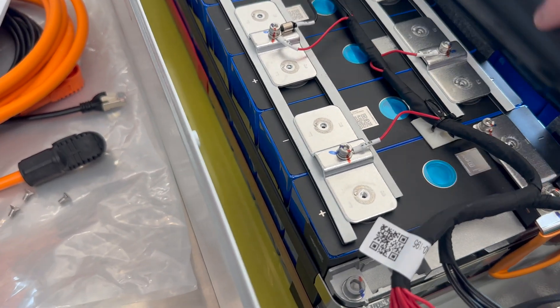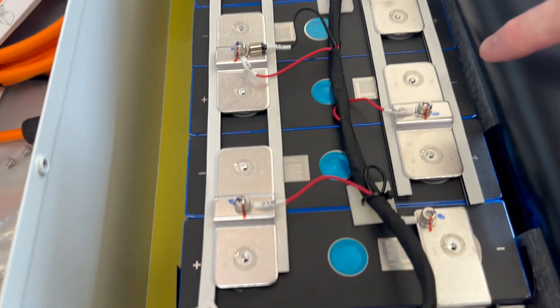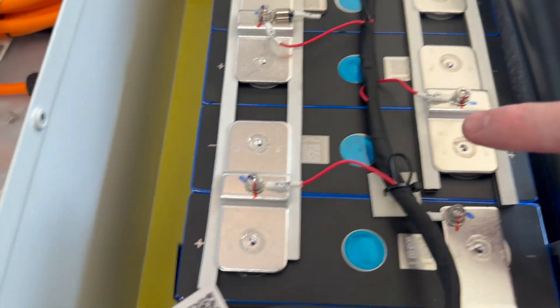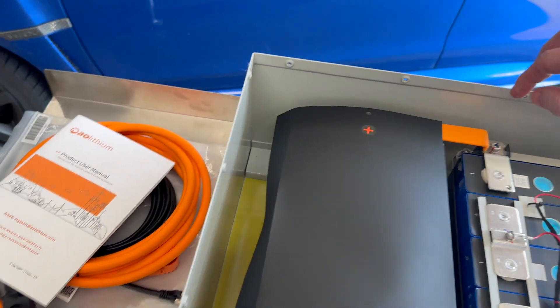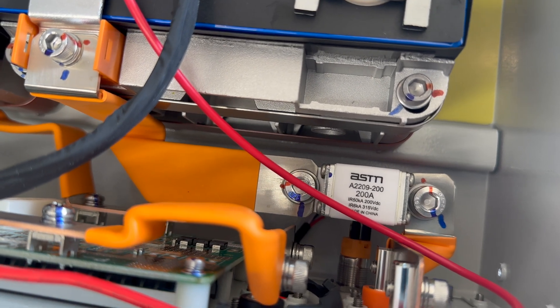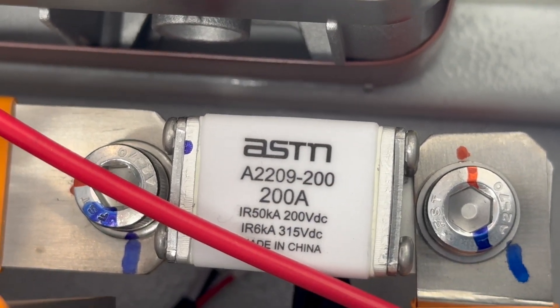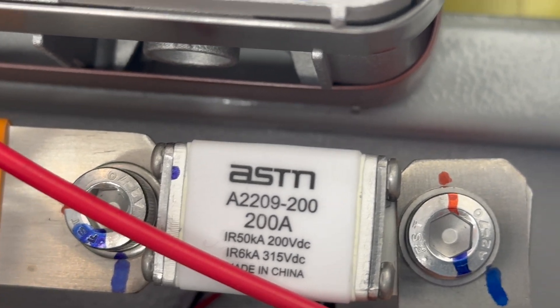The other side is the exact same thing — all wire-loomed in there, stuck down. That is high quality. These are all torque marked; there are actually two marks — looks like a blue mark and then a red mark. Let's look at the BMS and the back: the jumper between the cell banks is a flexible bus bar. Up at the BMS, there is also the main fuse — ASTN A2209, 200 amp, 50 kA (50,000 amp) interrupting.